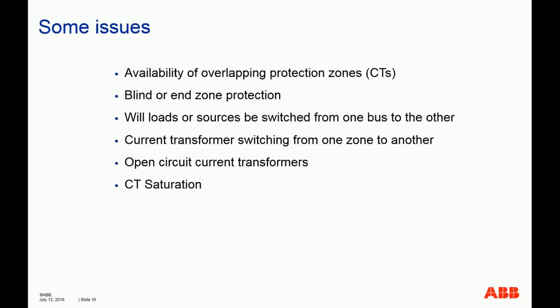So what are the issues about bus bar protection? First of all, you need to have enough CTs, and you need to have designated bus protection zones, and then you need to watch out for the so-called blind zone or end zone protection, which we will introduce a little bit later. And I have mentioned the critical special bus configurations, such as the single bus, double bus, single breaker. The load or feeder can be switched. The CT can be switched to either bus. So you need to be able to switch the CT. Okay. And what happens when the current transformer is saturated or it's open circuited? How would the bus protection deal with it? So these are all issues that need to be addressed by bus protective relays.